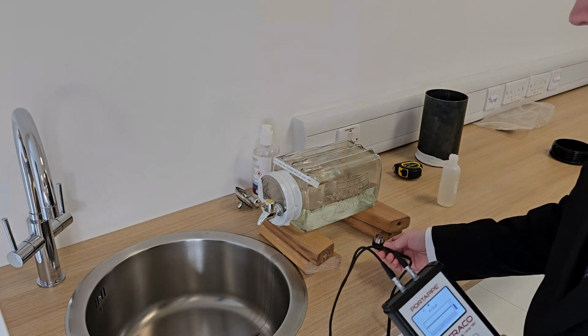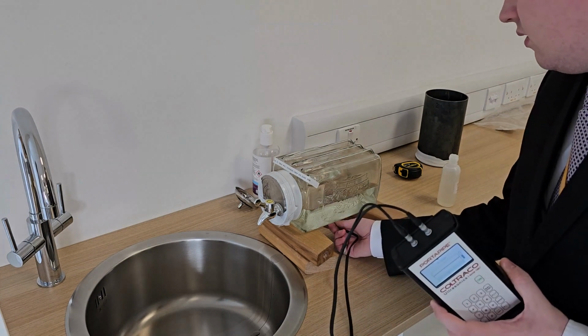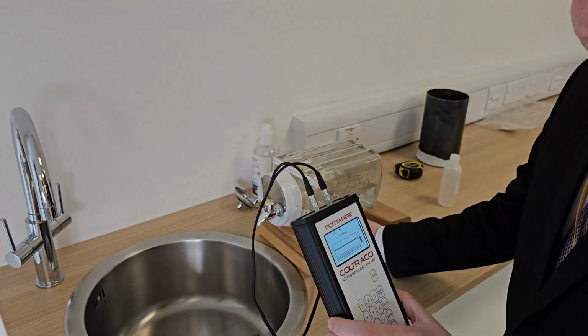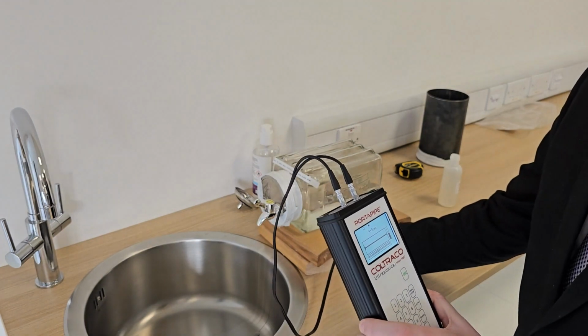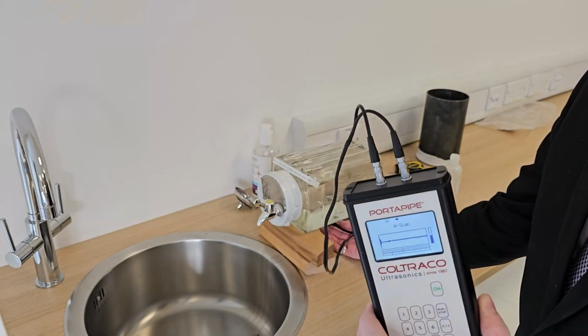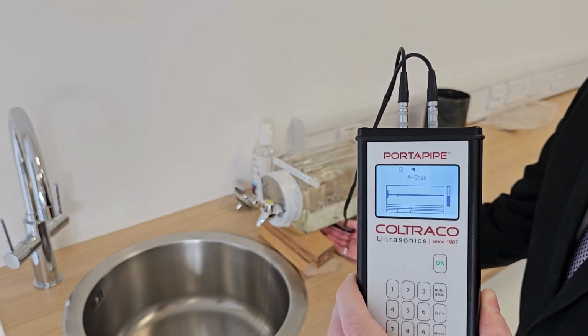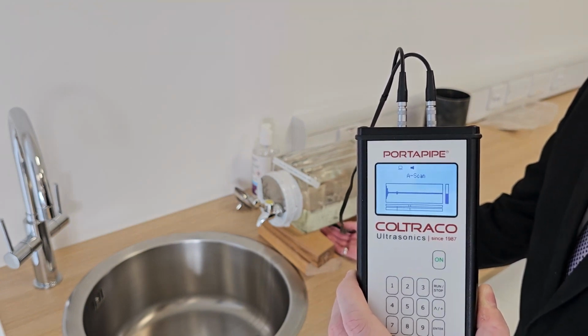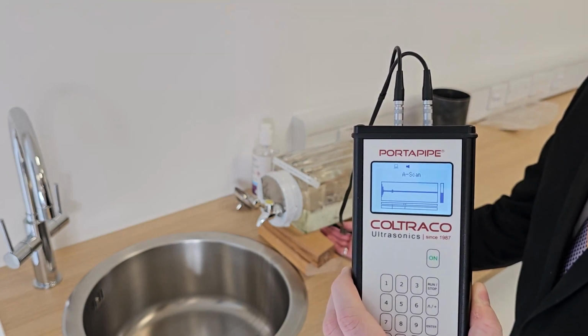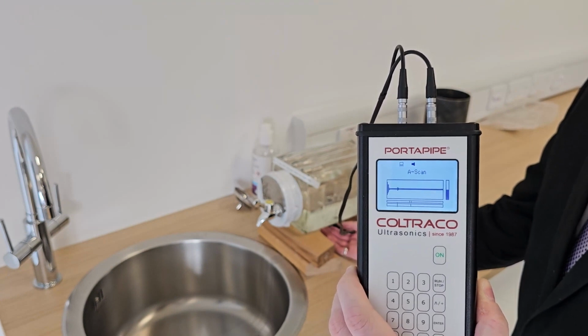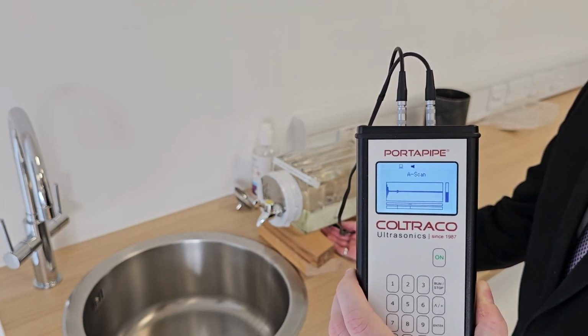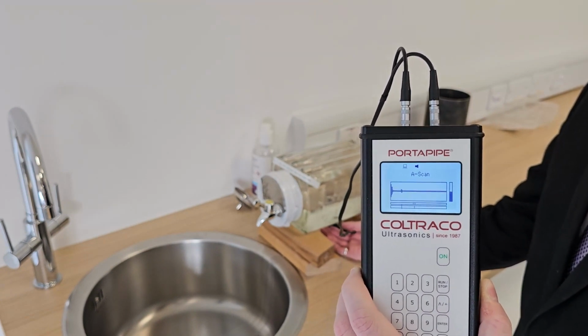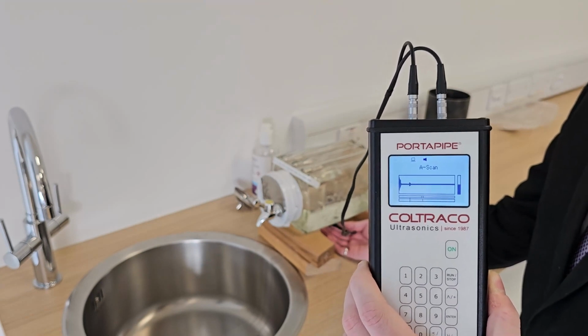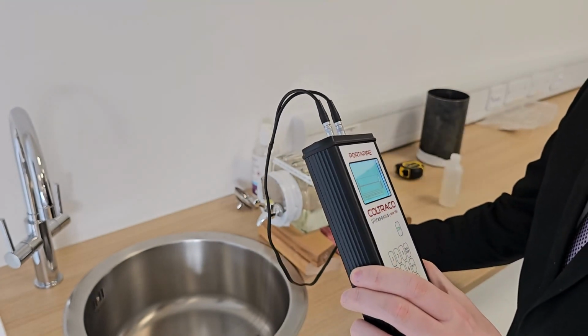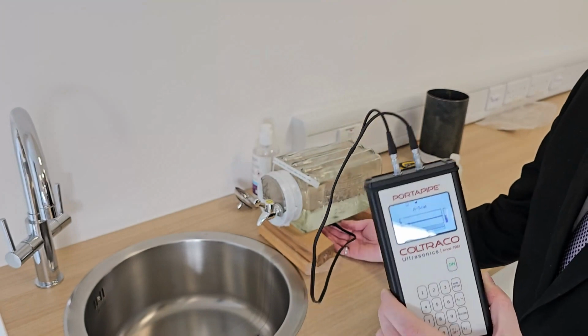With that done, we're now ready to place our sensor on the underside of this container, and then we can observe the A-scan to see if we can identify a reflection. As you can see, we have an initial period of some ringing on the far left-hand side of the waveform, and then a little further on, maybe 20% of the way along, we see a little bump in the readings. It's not very clear, but it's more than clear enough for the device to detect.